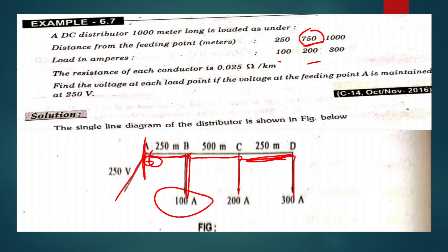The resistance of each conductor is 0.05 ohms per kilometer, so the resistance value R is 0.025 ohms. Find the voltage at each load point if the voltage at the feeding point A is maintained at 250 volts. The supply is 250 volts and the loads are 100 amps, 200 amps, and 300 amps.